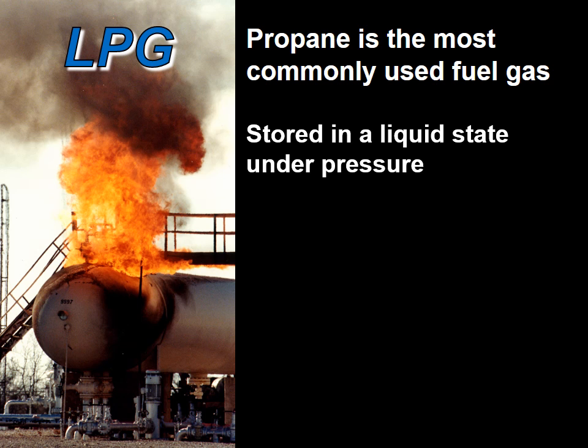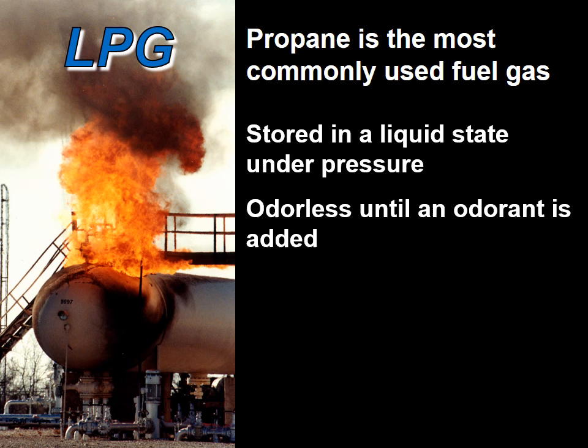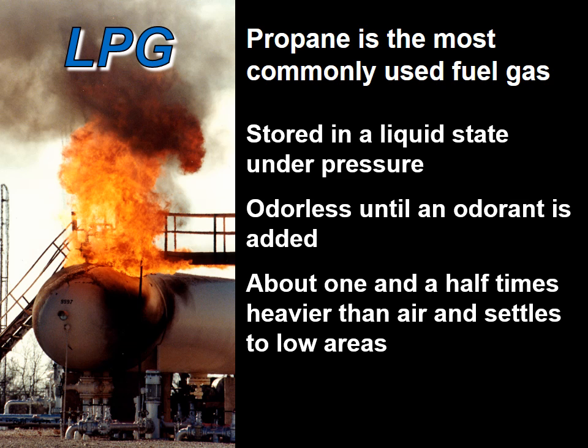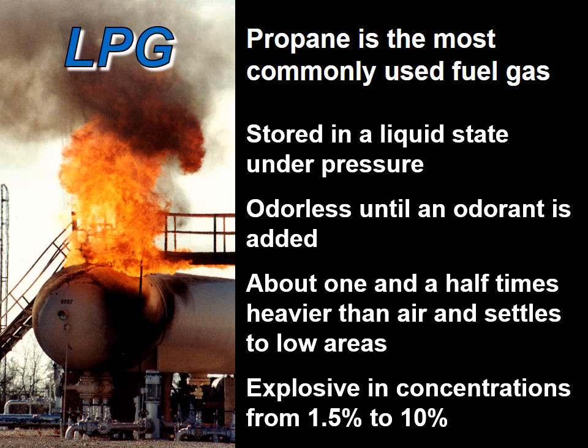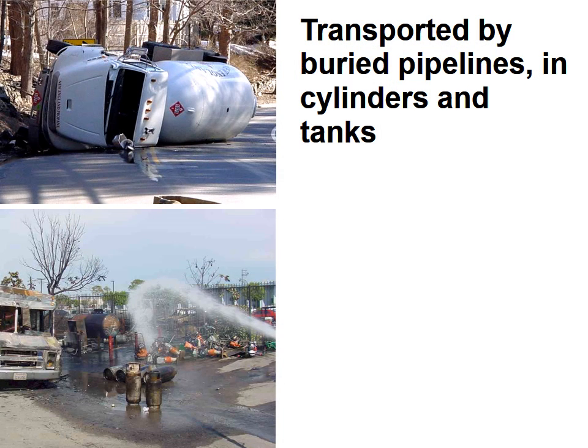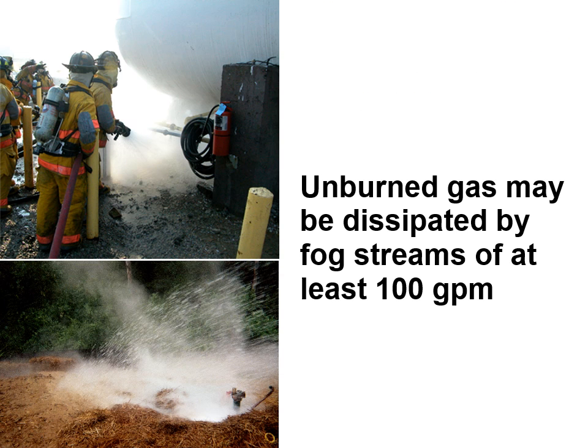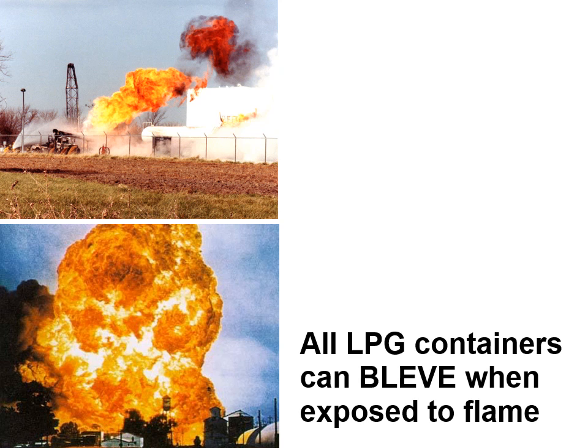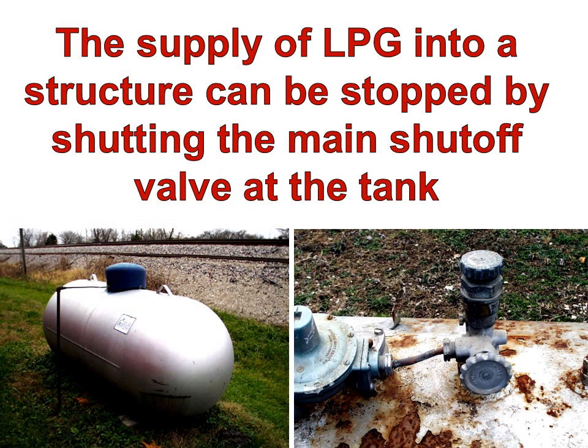Liquid propane gas. Propane is the most commonly used fuel gas. Stored in a liquid state under pressure, it is odorless until an odorant is added, which would be the mercaptan again. It is about 1.5 times heavier than air and settles to low areas. Explosive in concentrations from 1.5 to 10%. It can be transported by buried pipelines, in cylinders, and in tanks. Unburned gas may be dissipated by fog streams of at least 100 GPM. All LPG containers can BLEVE when exposed to flame. A supply of LPG into a structure can be stopped by shutting off the main shutoff valve at the tank.